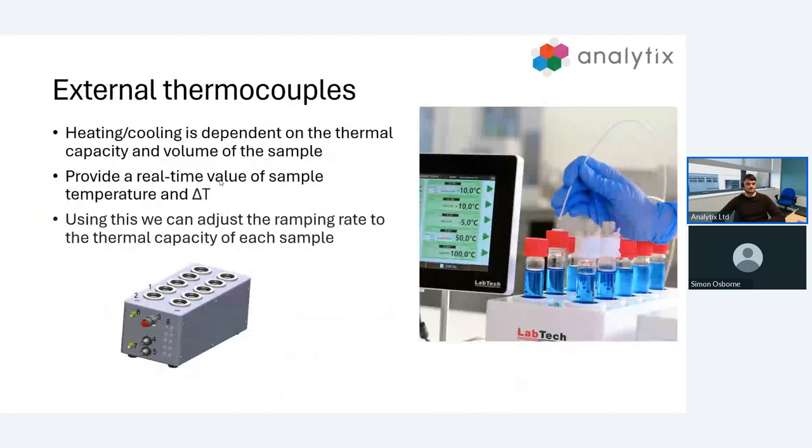External thermocouples are a really useful accessory that most of our customers like to use. Sample heating and cooling is dependent on a number of factors including the thermal capacity of your sample and the actual volume you're using. This is often overlooked. There's always going to be a disparity between your heating element temperature and your sample temperature.